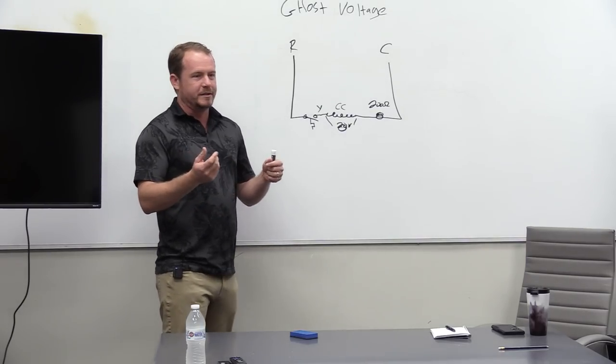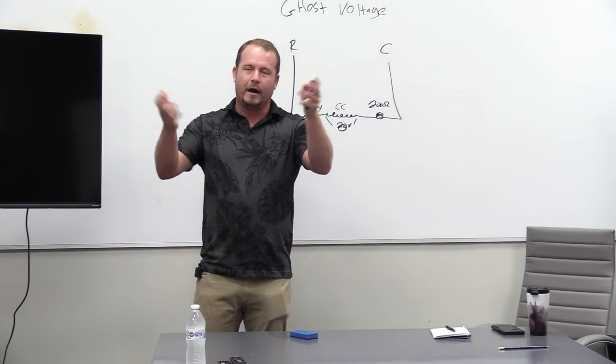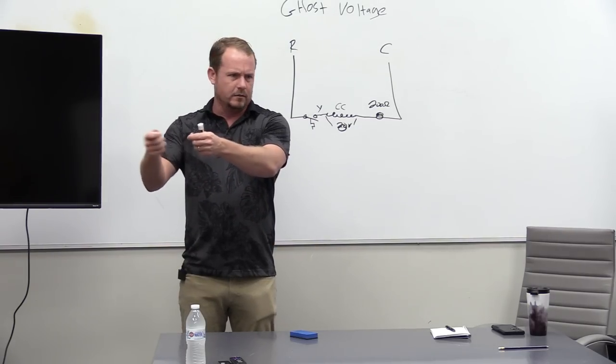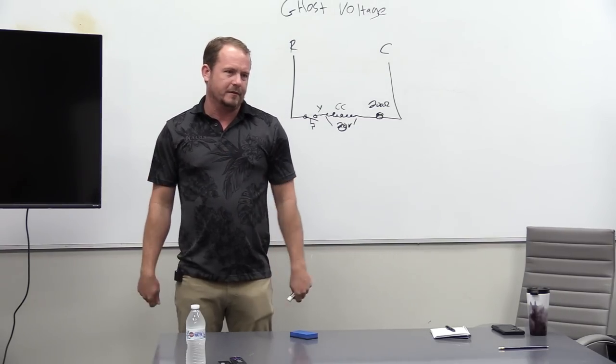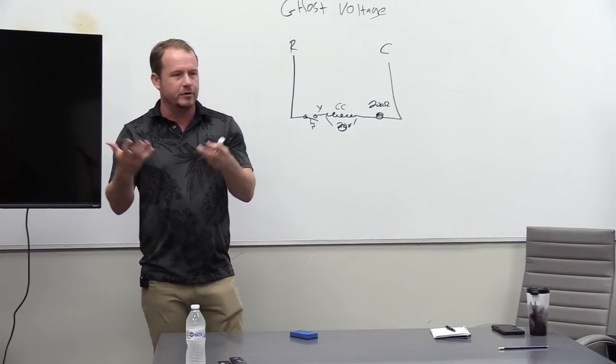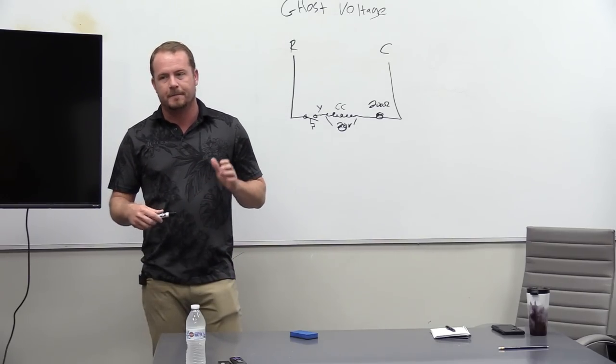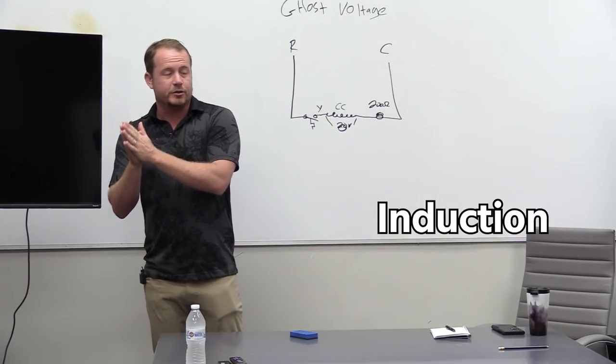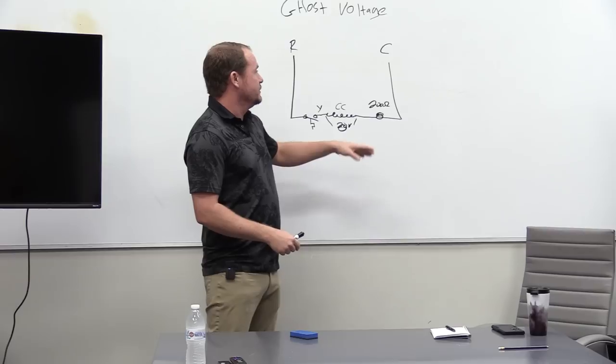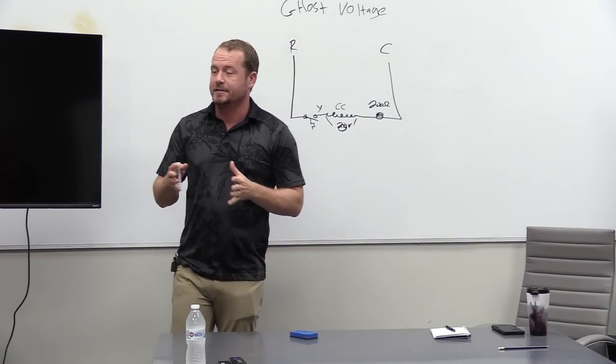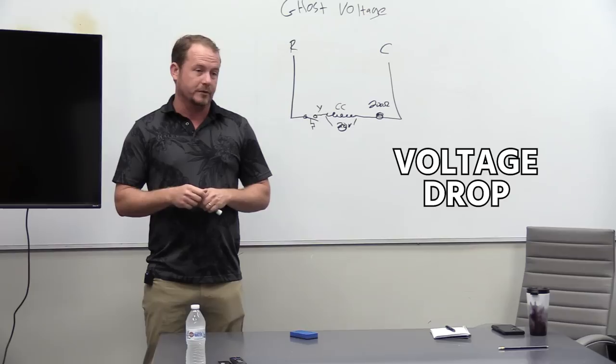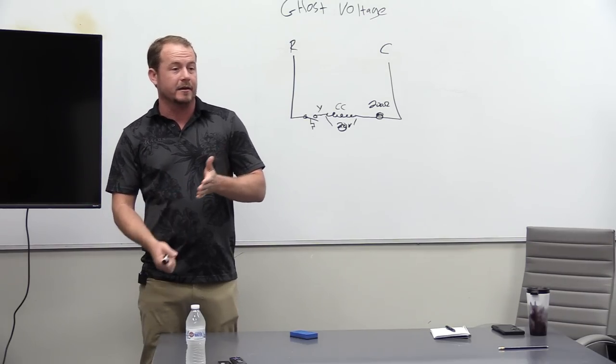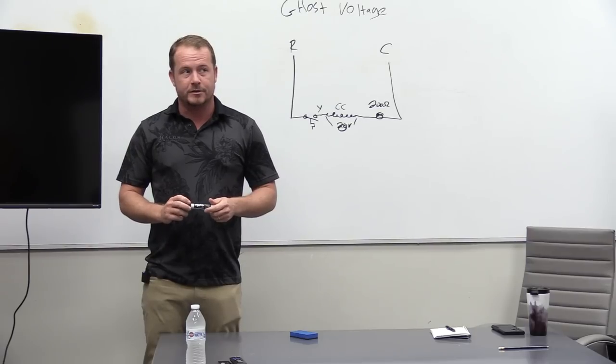And what you can do, and this is something that a lot of us have learned, it's not always going to be the contactor coil. You can actually use something like a contactor coil or a relay coil, basically in place of a meter that can become a low Z meter. Imagine if you take the coil on a relay, a 9340 or a contactor, you connect two wires to it, and you use that to test the system. Pulls in, you have 24 volts. Doesn't pull in, you don't have 24 volts. That's basically a low Z voltmeter. Because your voltmeter in these cases just becomes ineffective when it's not energized.